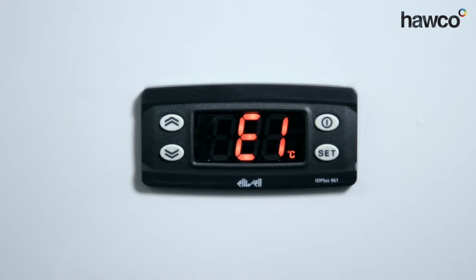Hello, we're talking about the Eliwell ID Plus 961. We're going to be talking about how to select the right probe. Sometimes when you turn up to a site and you see the controller showing E1, it's saying that the probe is incorrect or the probe is faulty. So we're going to go through to make sure it's set up to the correct probe and then hopefully everything should be okay.